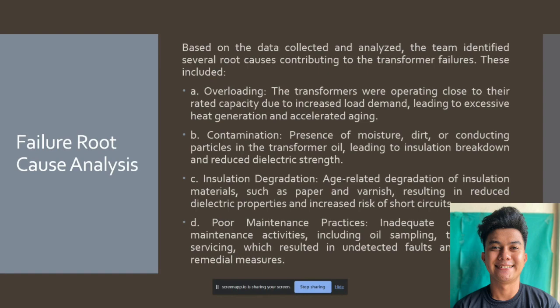Letter C is insulation degradation. Age-related degradation of insulation materials, such as paper and varnish, resulting in reduced dielectric properties and increased risk of short circuits. And the last is poor maintenance practices. Inadequate or irregular maintenance activities, including oil sampling, testing, and servicing, which resulted in undetected faults and improper remedial measures.